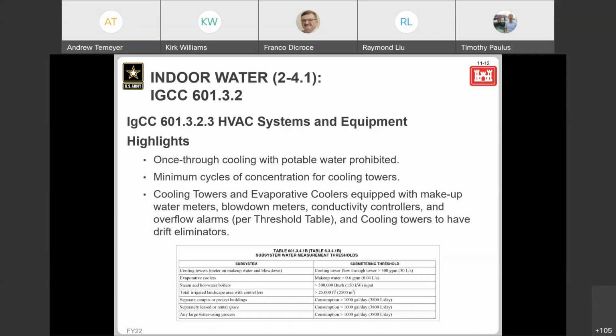Next one is minimum cycles of concentration for cooling towers. For those of y'all that don't live and breathe HVAC, in simple terms this is how many times the cooling tower is going to recirculate the water before backwashing. The criteria has different settings based on your makeup water, or the potable water that's coming in, and the hardness, or calcium carbonate. The typical ranges are going to be 3 to 5 cycles of concentration that you see with the criteria.